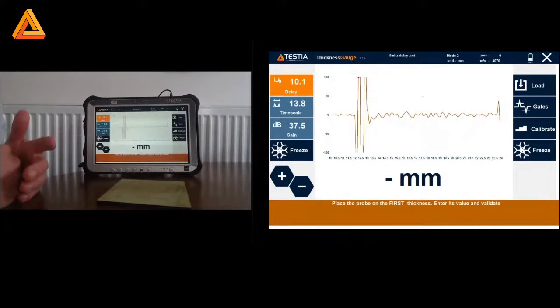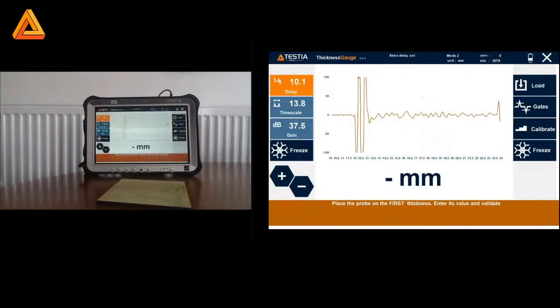We can use it, so the flaw detector can be used by an expert, level 2, level 3 maybe, and they can confidently pass over a thickness gauge module set up by them with reduced ability to make alterations, and confidently know that they can go ahead and use the instrument to perform the inspection as well.